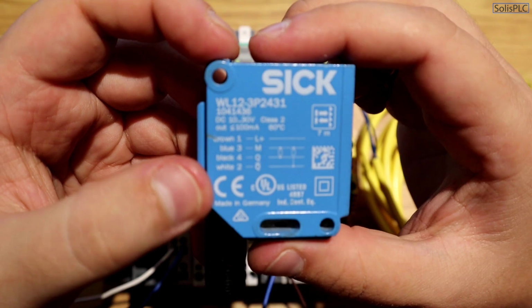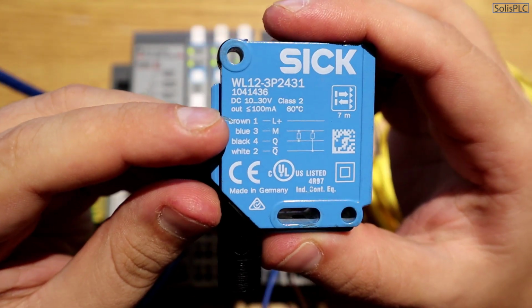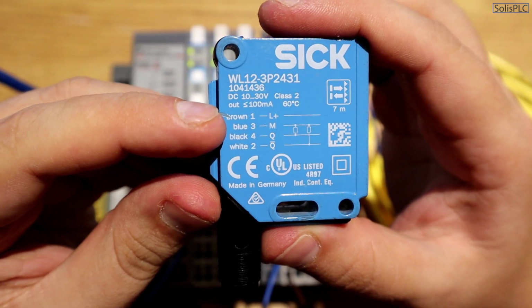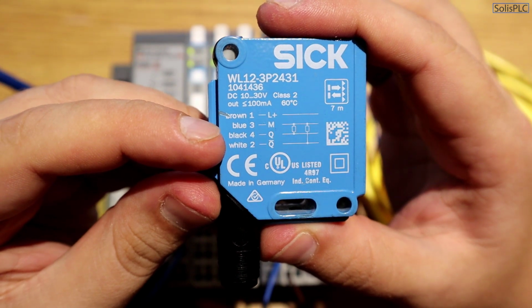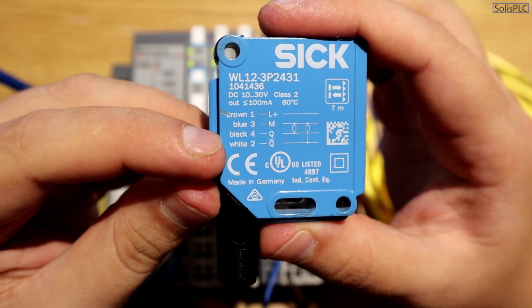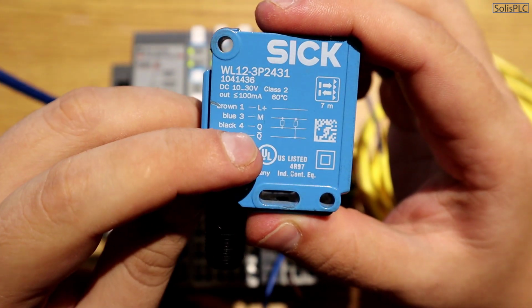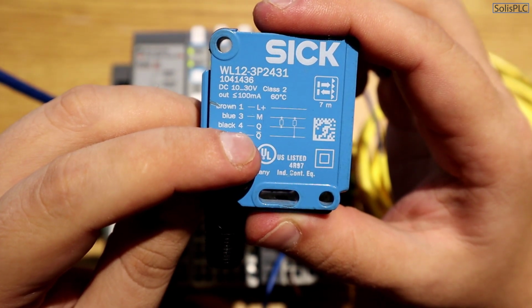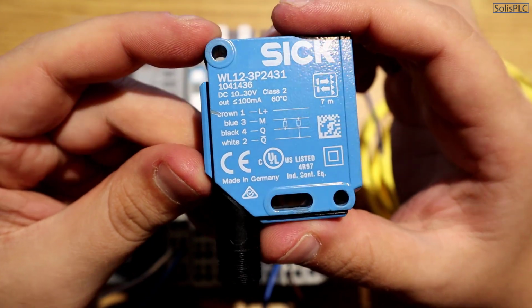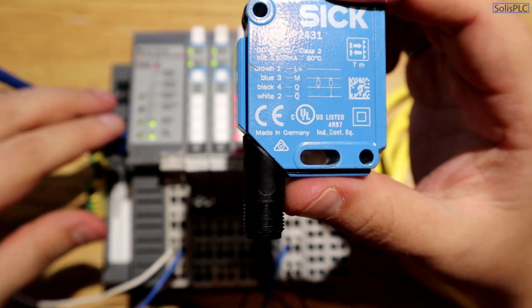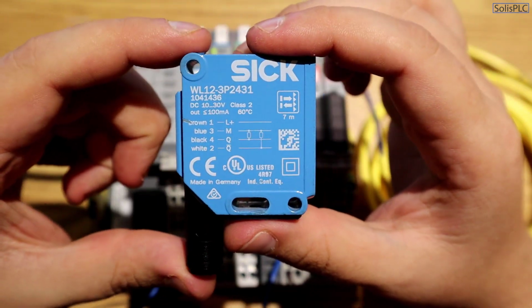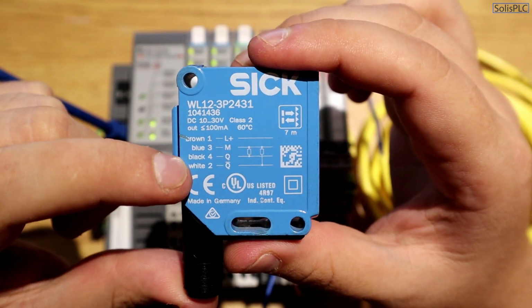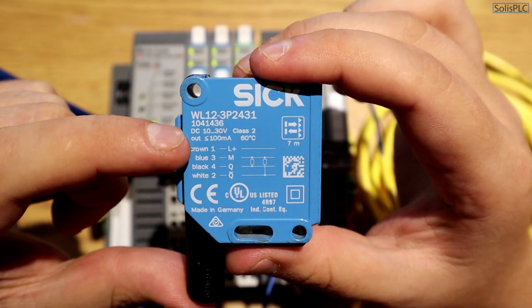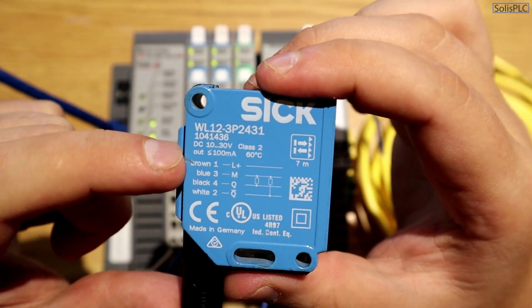And if we look at their descriptions, the brown is essentially going to be our 24 volts. The blue is going to be our ground or 0 volts. Then we have the black and the white, which are going to be essentially the signals sent back from the sensor to our PLC system. We'll look at the wiring in just a second, but it's very important to understand that the sensor needs to match the appropriate card. And in this case, we'll look at the voltage.